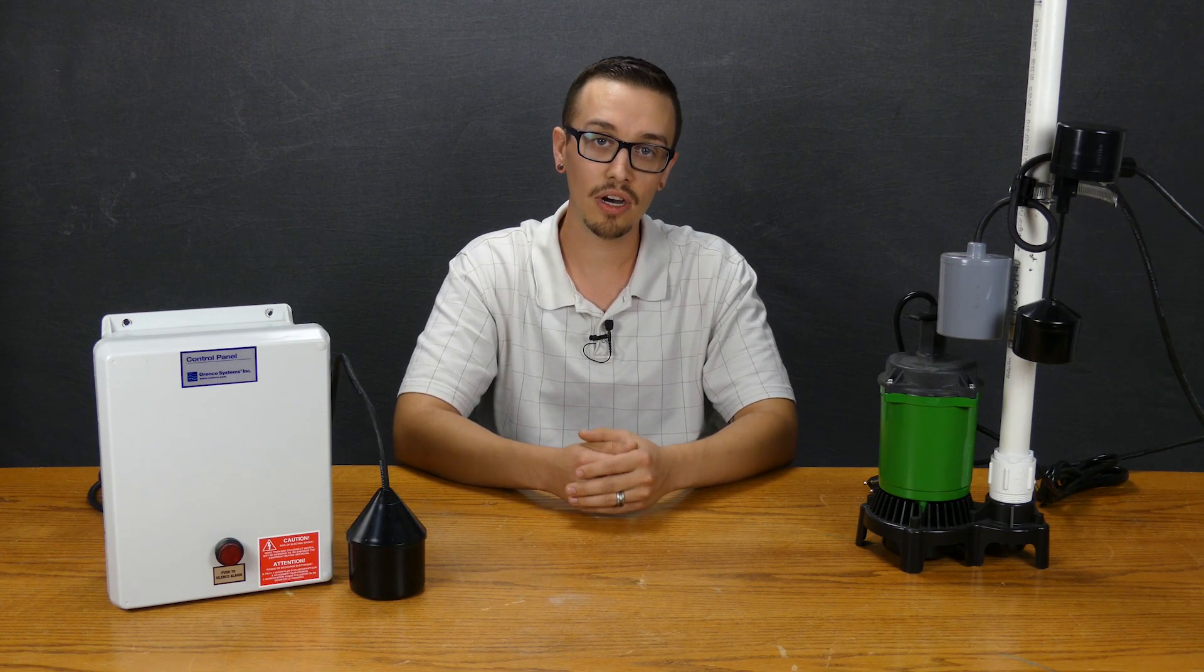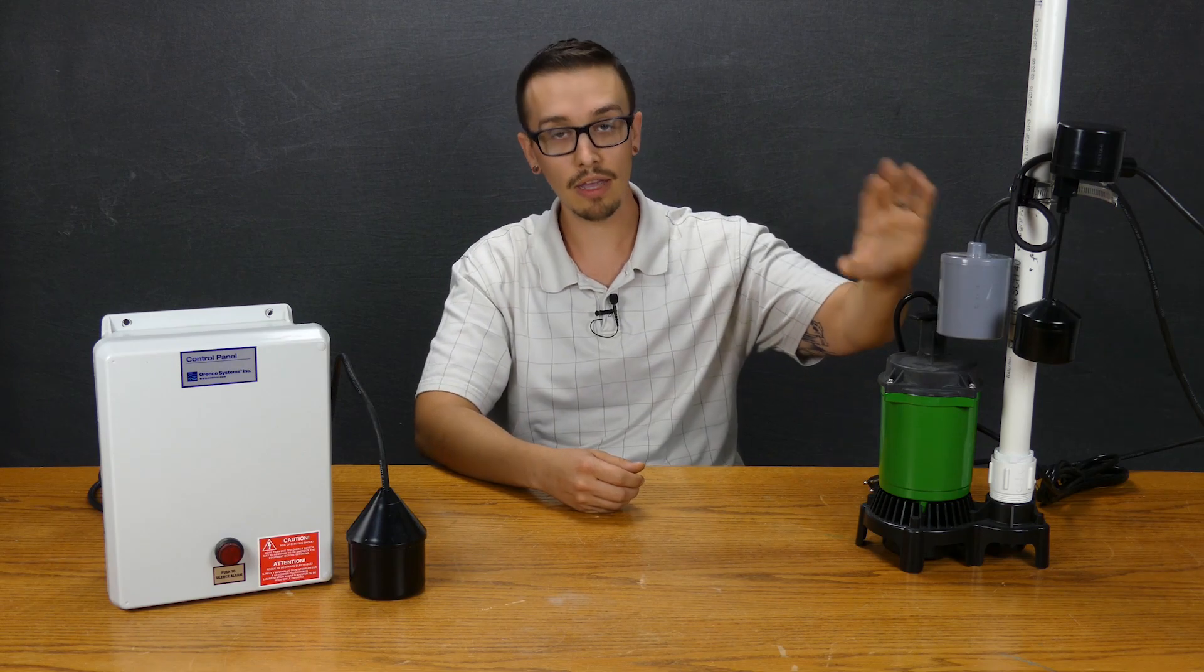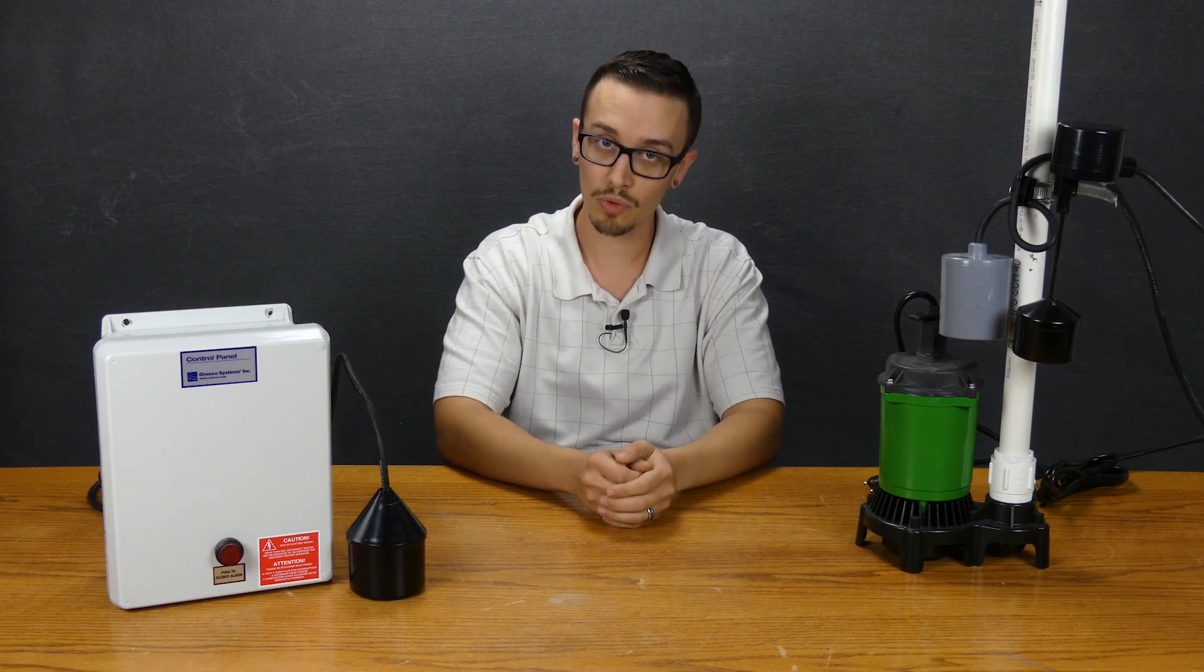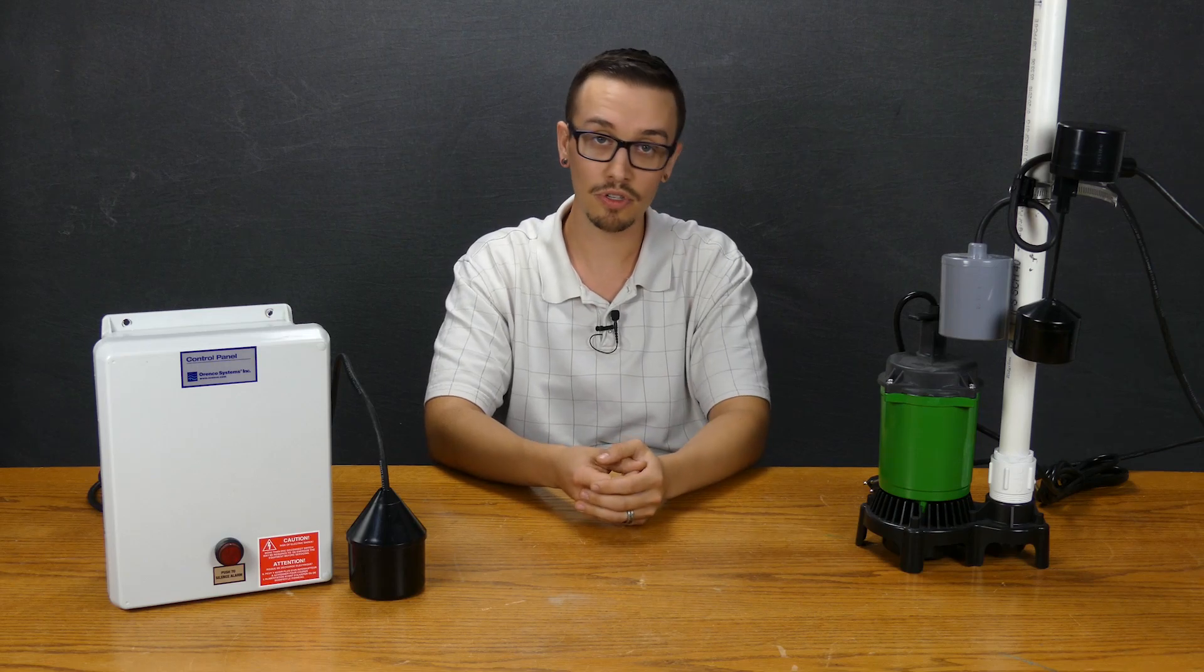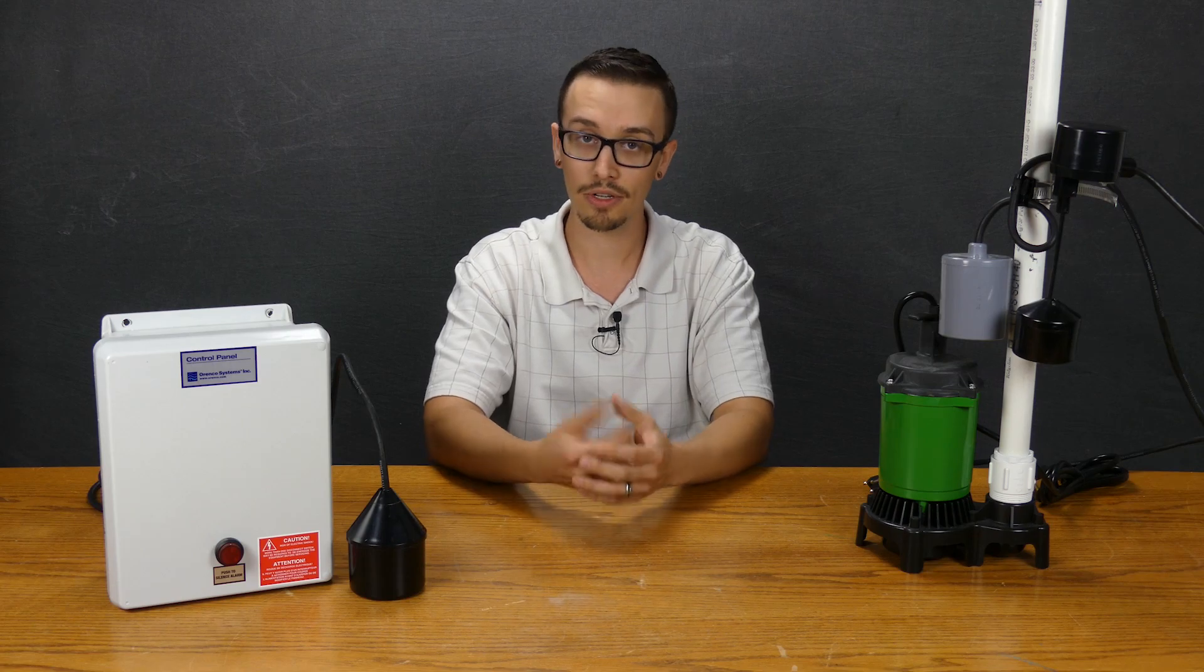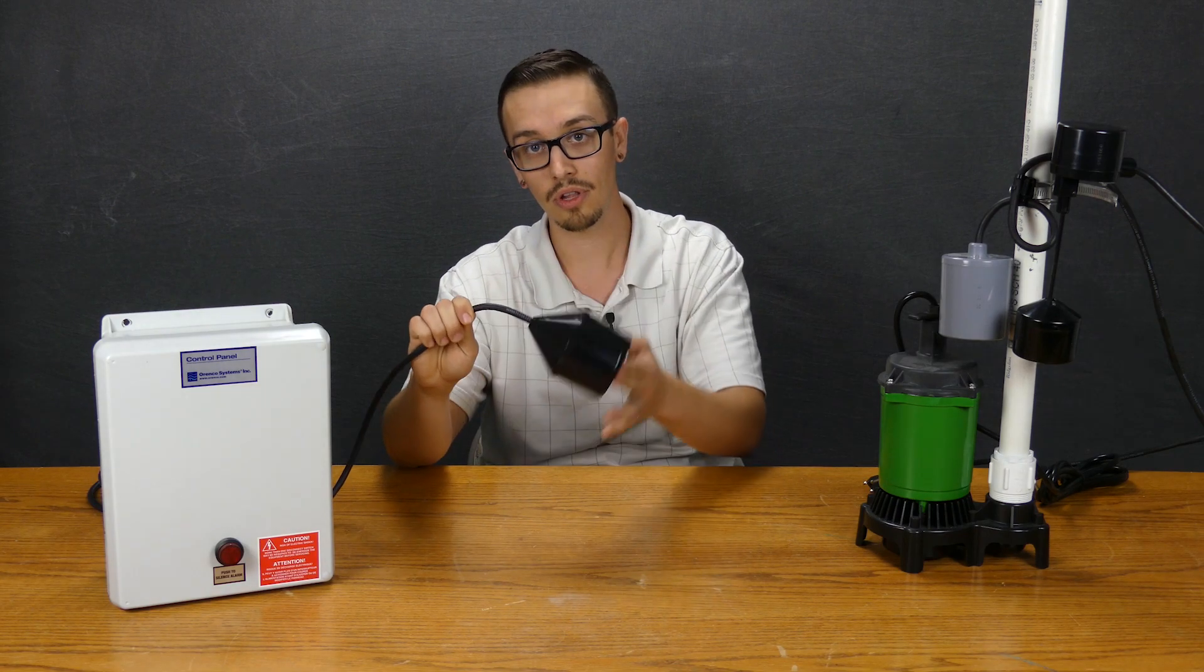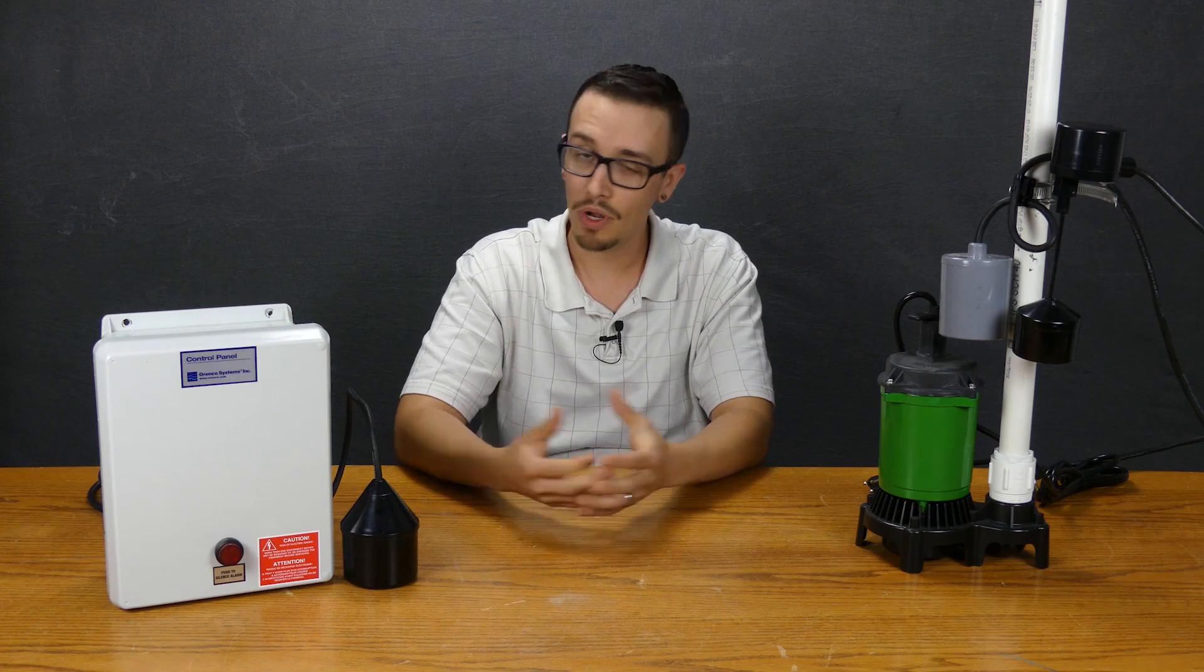On the topic of tether length and float travel and so forth, with a pump control switch the longer this tether, the more travel that float switch is going to have. So that of course makes pump control switches a little more susceptible to getting hung up with other floats or objects in the tank, whereas a control switch typically only has a very short tether, maybe an inch and a half to three inches. So there's a lot less movement and a lot less chance of something going wrong.